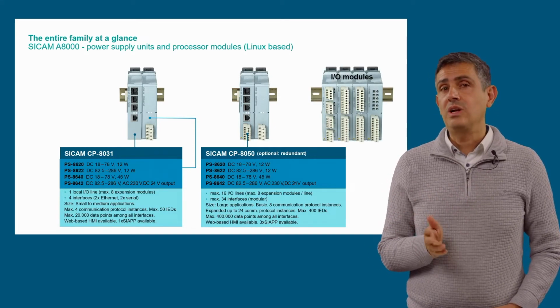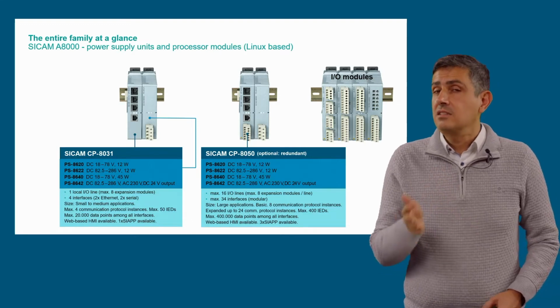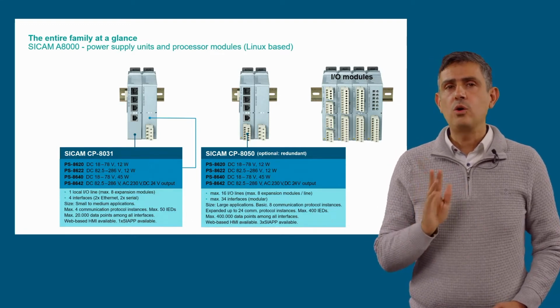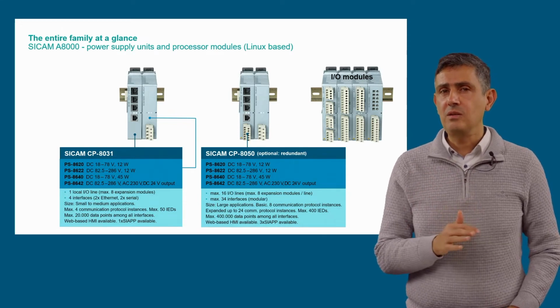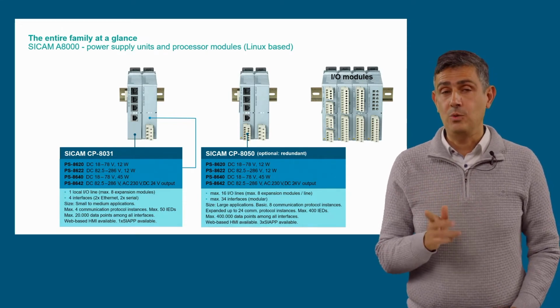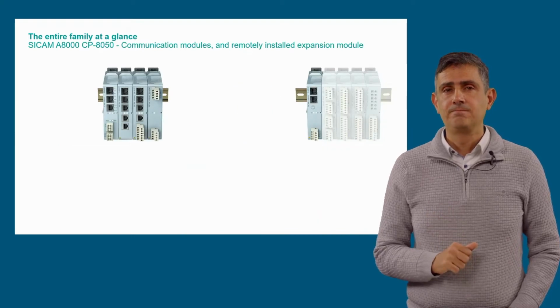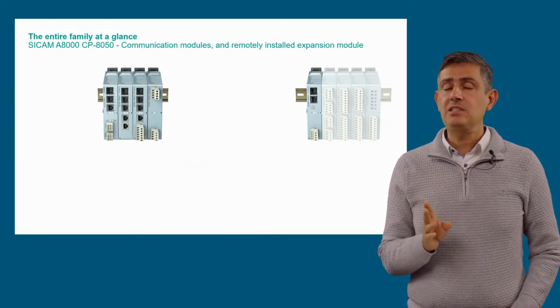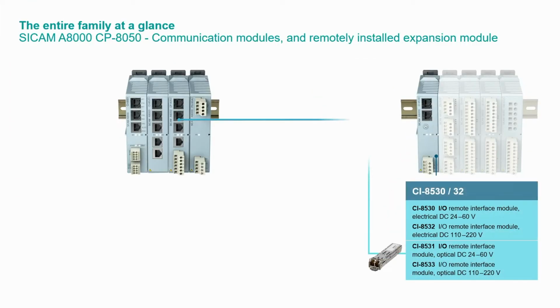Attached to the CPU, you can add also up to 8 I/O modules exactly as in the smaller RTUs. Also, all modules available for the smaller RTUs are available for the CP8050 or for the CP8031. But the CP8050 is not limited to only 8 I/O modules. Up to 15 external rows of up to 8 I/O modules each can be included on one RTU through remote interface modules like the CI8530. These modules can be connected to the LAN ports of the CP8050 to extend the bus both with electric LAN cable or via fiber optic, and also provide the power supply for the I/O modules on the row.